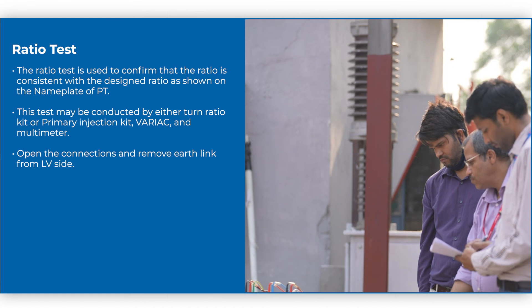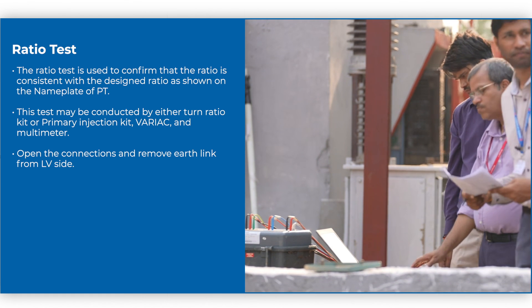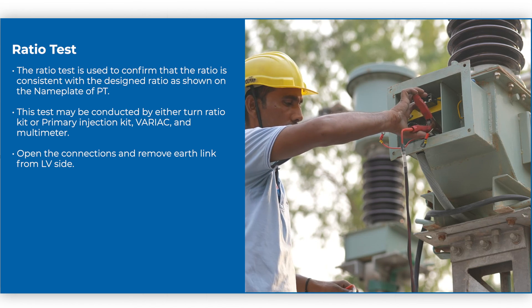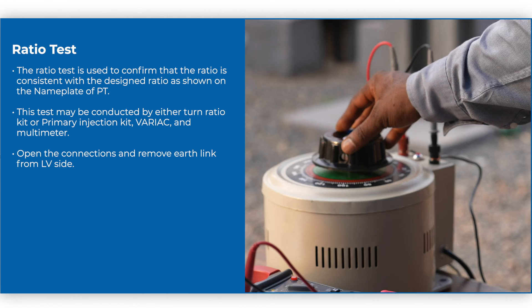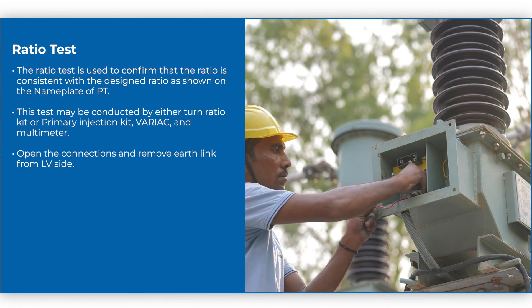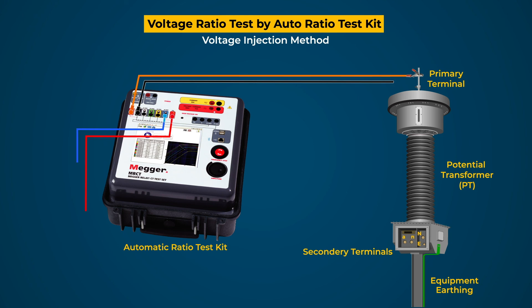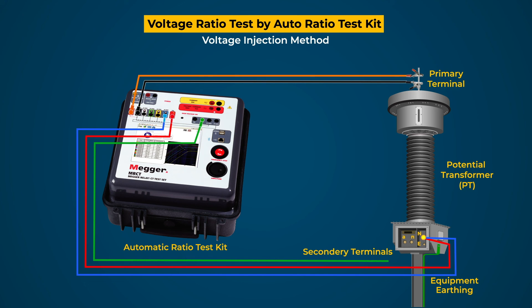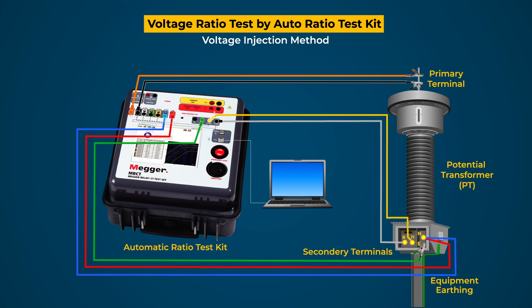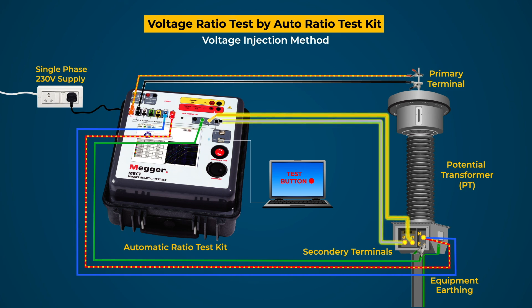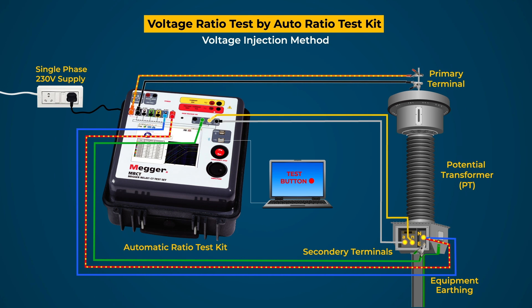Ratio test: The ratio test is used to confirm that the ratio is consistent with the designed ratio as shown on the nameplate of the PT. This test may be conducted by either a turn ratio kit or a primary injection kit, variac, and multimeter. Open the connections and remove the earth link from the LV side. For the auto ratio test kit method, connect the primary injection leads of the test kit to both primary terminals and connect the earth terminal of the test kit to PT earthing. Connect the secondary leads to the secondary winding terminals. Connect the single phase 230 V AC supply to the test kit. Apply the test voltage across the primary terminals; the kit measures the induced voltage in the secondary winding and calculates the ratio and percentage error of the PT. Record the displayed value and compare with the designed ratio. If found beyond the permissible limits, take corrective actions.